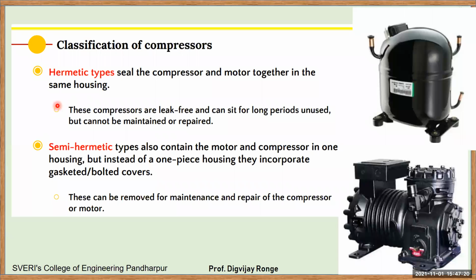Then, depending on the construction, they are further classified as hermetic type and semi-hermetic type. Okay. So hermetic type seals the compressor and motor together in the same housing. So we have the motor and compressor in the same housing. These compressors are leak free and can sit unused for a long period, but cannot be maintained or repaired. These are generally used in, say, water coolers. We make use of this kind of hermetic compressor.